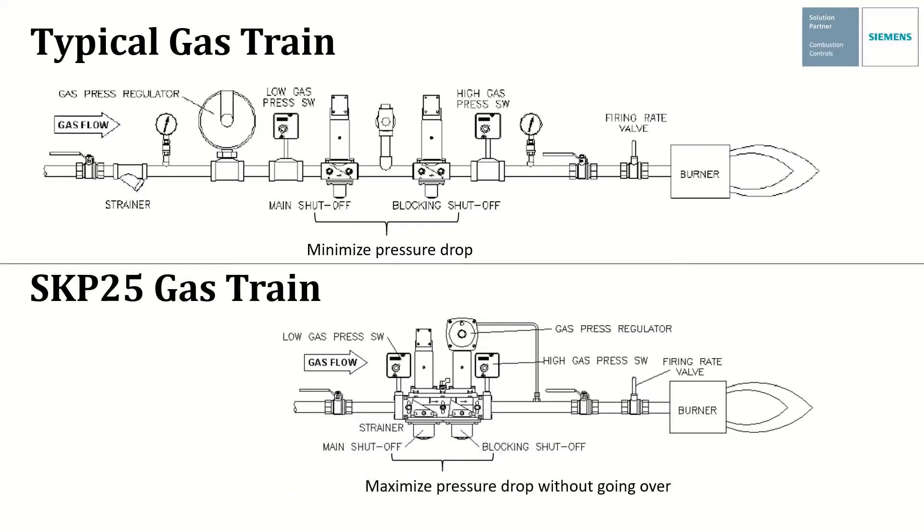Don't take too much pressure drop across the valve, then the top end capacity will be reduced. Since we don't want to size too small, it's important to know the inlet pressure to select the proper valve size.